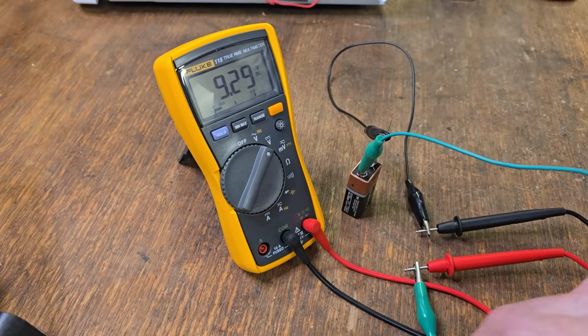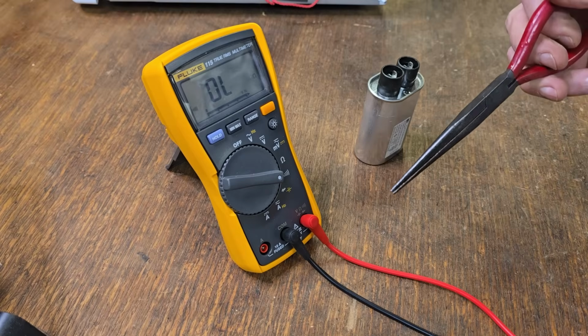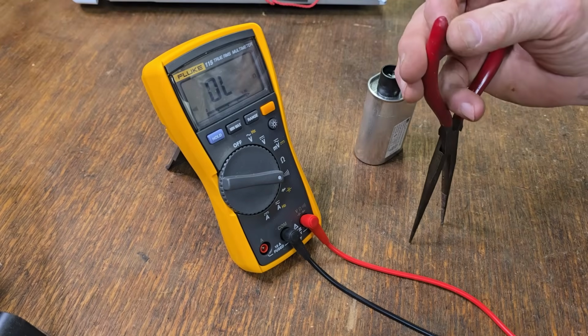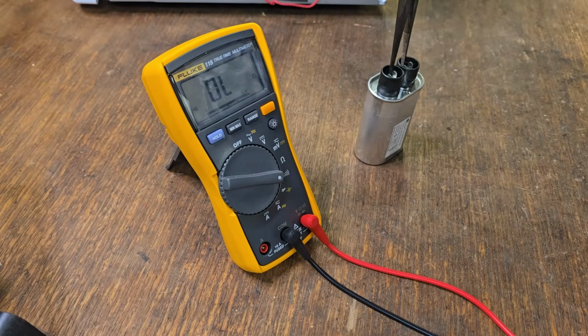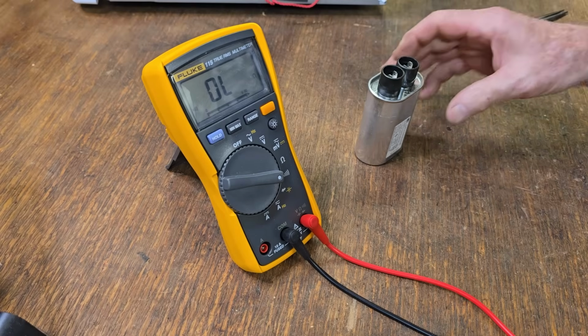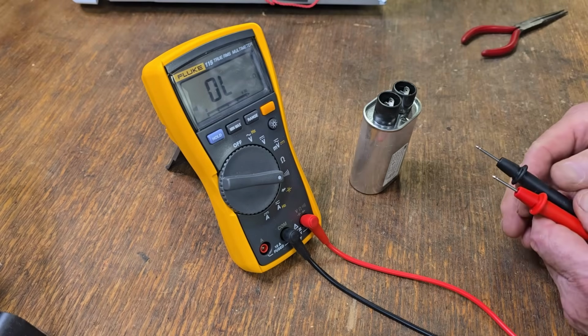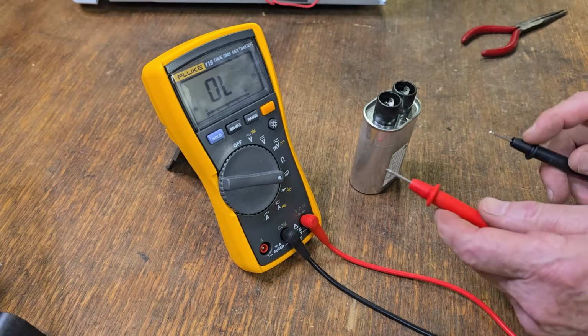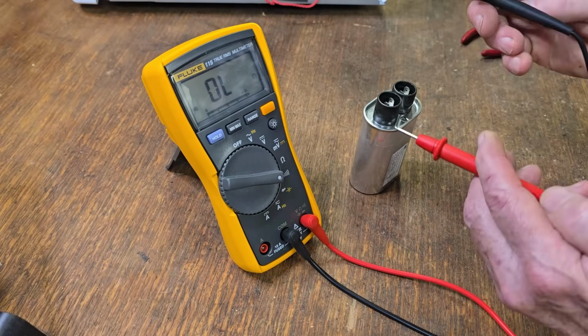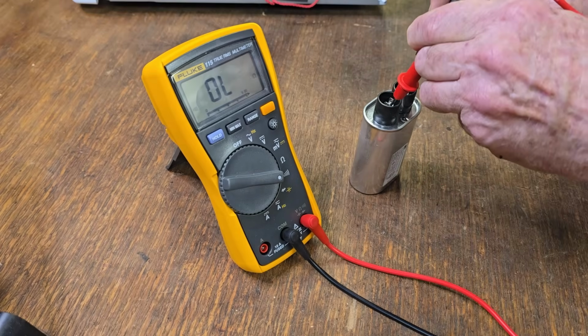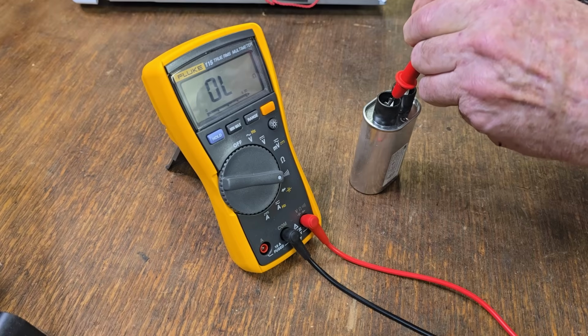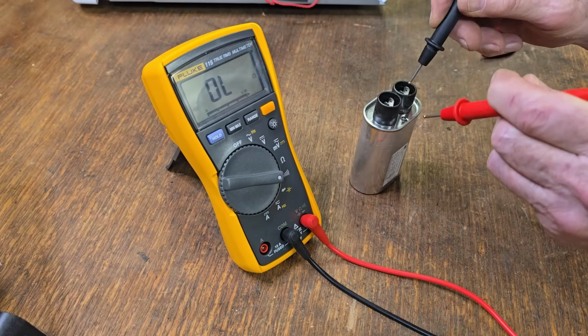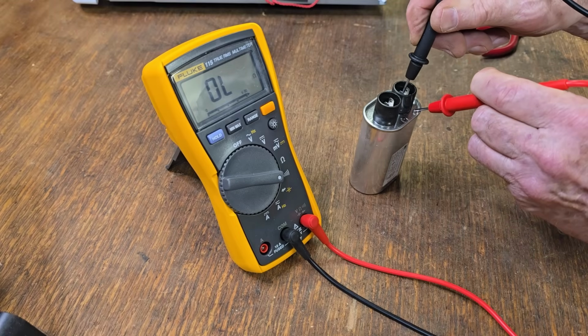I'll check our capacitor next. We can stick our insulated handled pliers across the terminals just to make sure there's absolutely no voltage left in there to harm our meter. But we have discharged it, so it should be perfectly fine. We've got it set to continuity test, and we should have nothing between the terminals, so it's not shorted, and nothing from either terminal to the case.